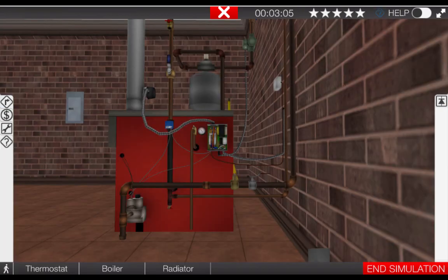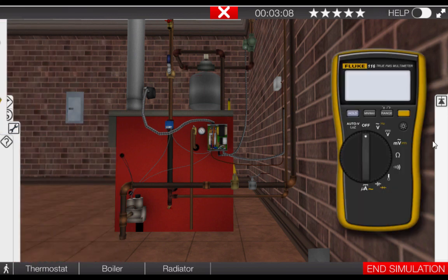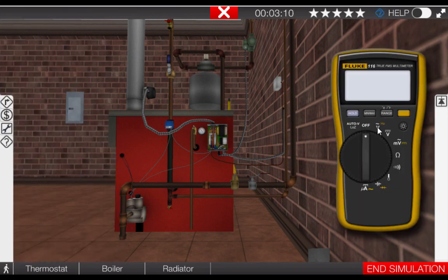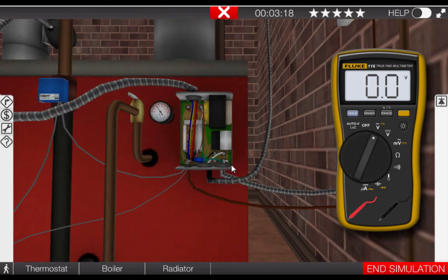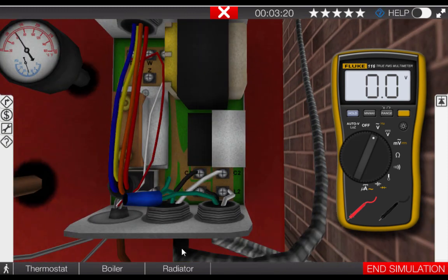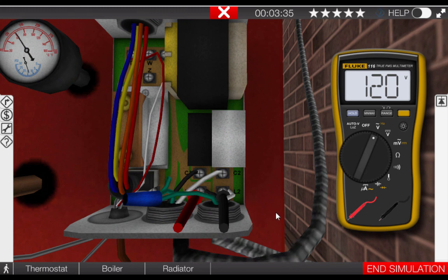Remove the digital voltmeter or multimeter from the toolbox — click on the meter icon and turn the selector dial to AC volts. Right-click on the combination aquastat and zoom in to easily identify the terminals. Click on one meter lead and place it on the glowing hotspot at the L1 terminal; place the black lead on the L2 terminal. Here we can see 120 volts coming to the aquastat from the service switch.